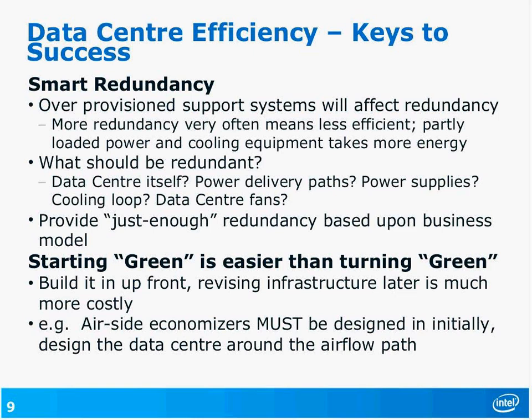The reason that this is really important is if you've over-provisioned your support systems, that affects redundancy. It means that things can be less efficient, with partly loaded power and cooling equipment, et cetera. What we want to do ideally is provide just enough redundancy.